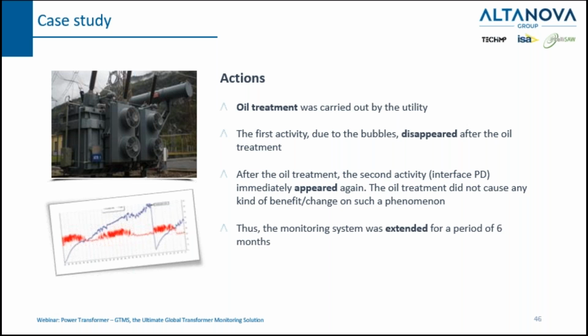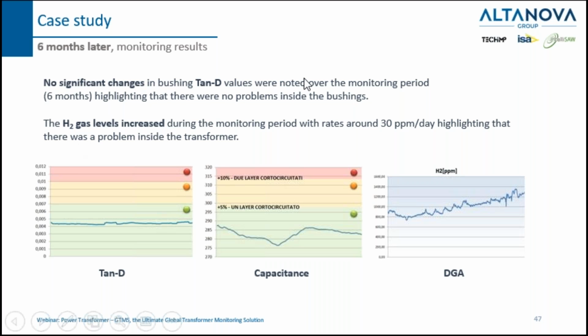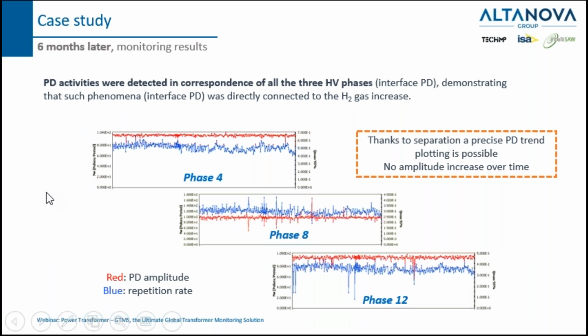For this reason, the utility decided to extend the installation of the monitoring system for another 6 months. Here you can see other results from the 6 months of monitoring regarding the tan delta. This line was almost stable. The capacitance value was also stable. And for the DGA, during these 6 months, we saw an increase of almost 30 ppm per day in the concentration of hydrogen detected by the DGA. Here are the parts relevant to PD.